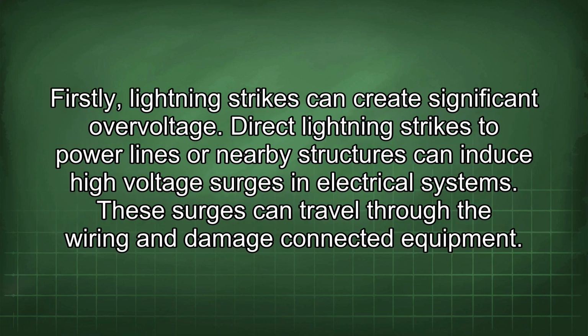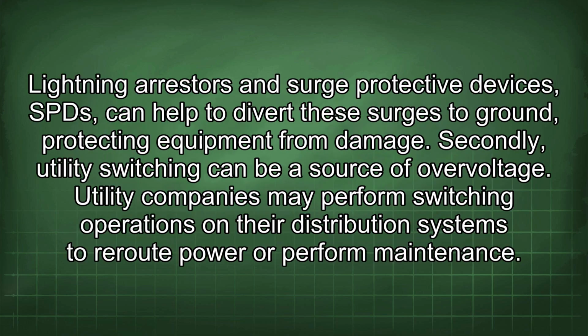Firstly, lightning strikes can create significant overvoltage. Direct lightning strikes to power lines or nearby structures can induce high voltage surges in electrical systems. These surges can travel through the wiring and damage connected equipment. Lightning arresters and surge protective devices, SPDs, can help to divert these surges to ground, protecting equipment from damage.